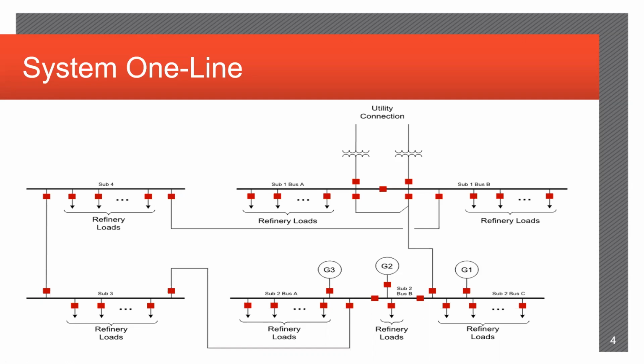Yep, great question. So typically these generators, whenever they're running in parallel with the utility, they're running in what is called droop mode. Essentially what would happen whenever a generator went islanded, the generator control system would tell one of the generators to go to isochronous mode, and then depending on whether or not they were in parallel with the isochronous generator, then the other two would either stay in droop mode or go to isochronous mode, depending on how the system was islanded.